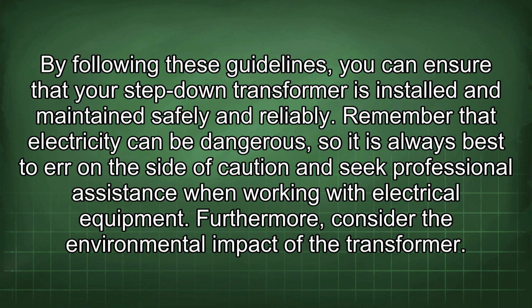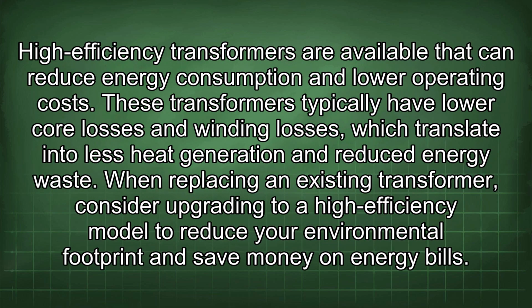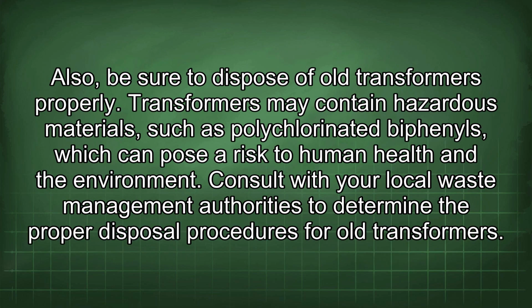Furthermore, consider the environmental impact of the transformer. High-efficiency transformers are available that can reduce energy consumption and lower operating costs. These transformers typically have lower core losses and winding losses, which translate into less heat generation and reduced energy waste. When replacing an existing transformer, consider upgrading to a high-efficiency model to reduce your environmental footprint and save money on energy bills. Also, be sure to dispose of old transformers properly.